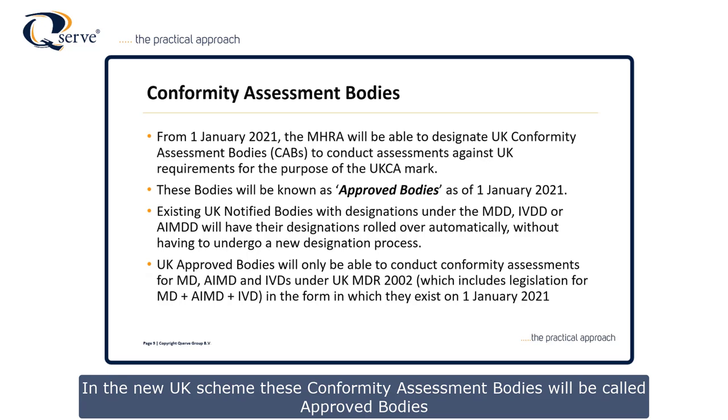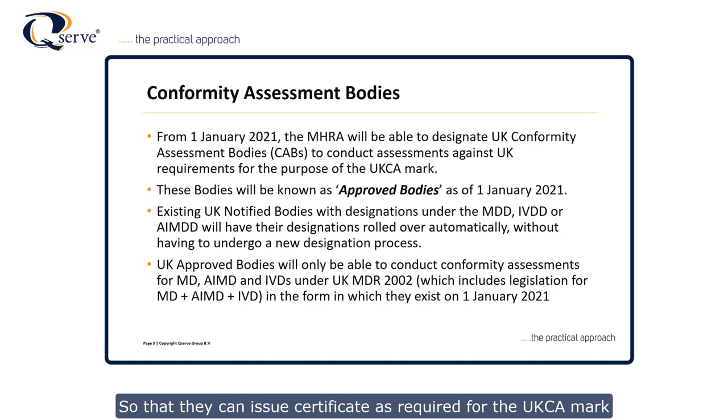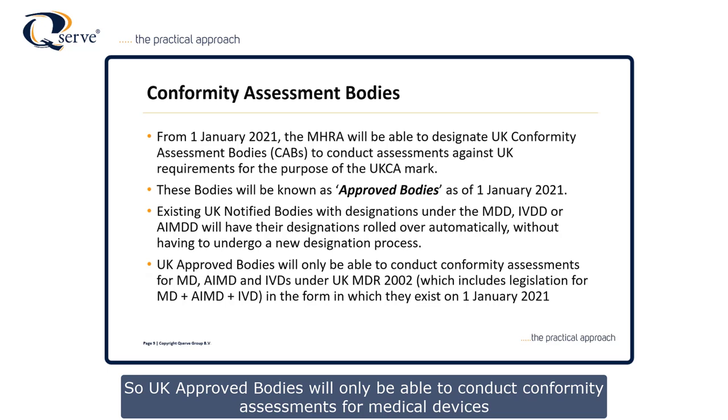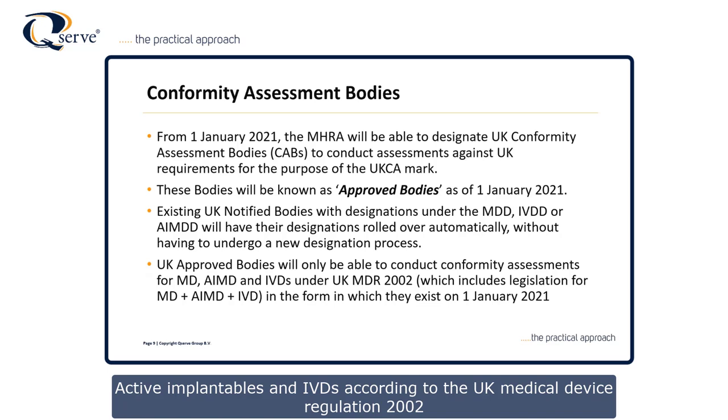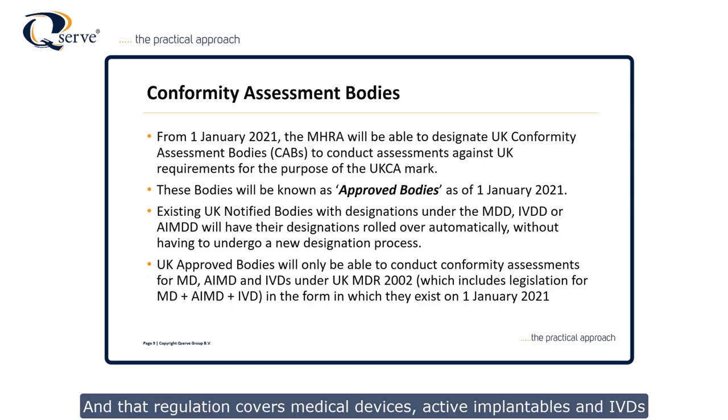In the new UK scheme, conformity assessment bodies will be called approved bodies. From the 1st of January 2021, MHRA will be able to designate UK conformity assessment bodies so that they can issue certificates required for the UKCA mark. Existing UK notified bodies will roll over their existing designations for medical devices, IVDs, or active implantable devices without having to go through extra designation processes. UK approved bodies will only be able to conduct conformity assessments according to the UK Medical Device Regulation 2002 — noting that although it's called a regulation, it is not the European MDR. That regulation covers medical devices, active implantables and IVDs, and will be in the form that exists from the 1st of January 2021, reflecting the directives as they stand.